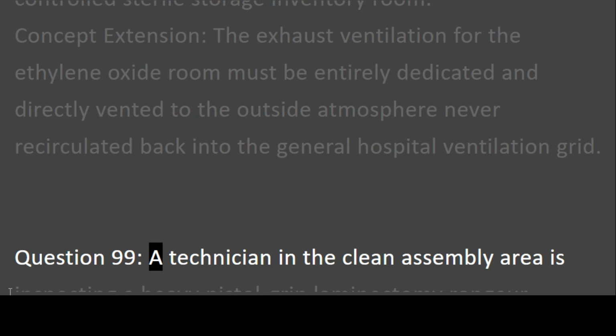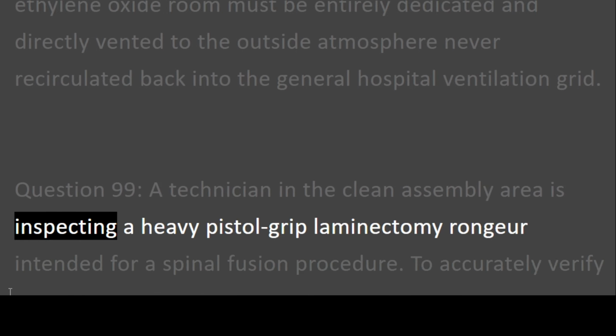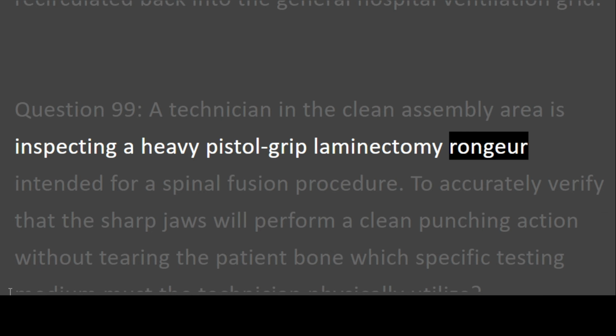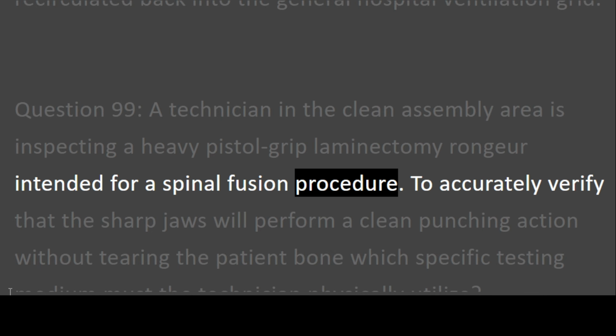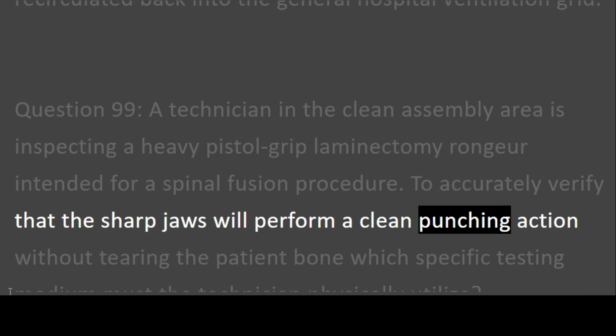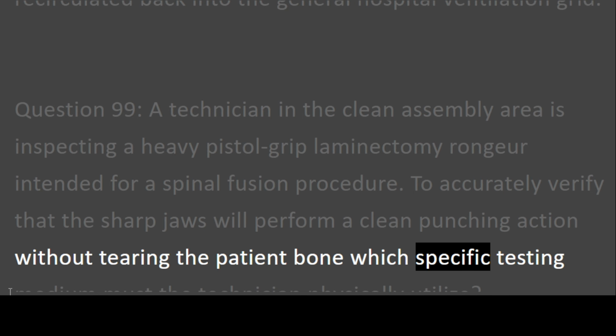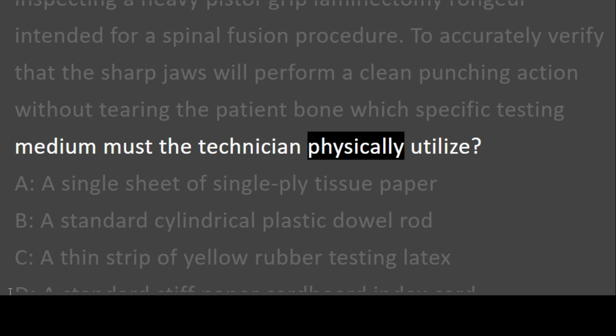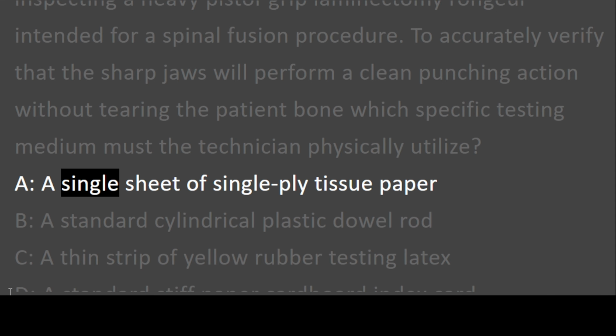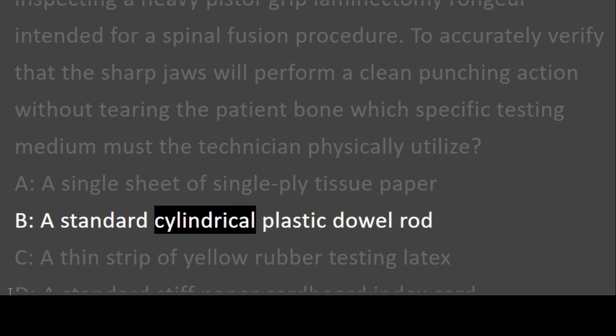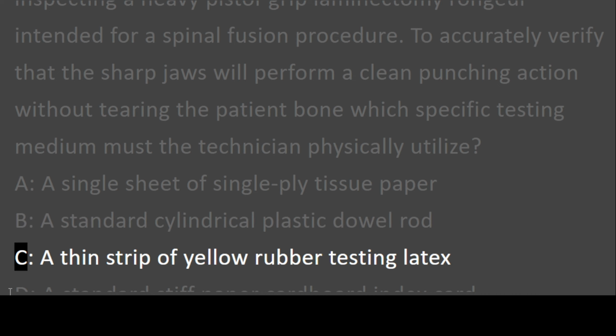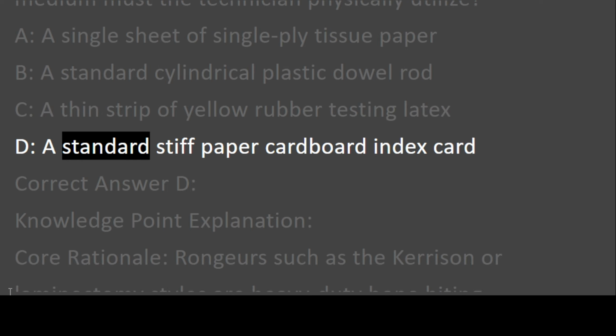Question 99. A technician in the clean assembly area is inspecting a heavy pistol grip laminectomy rongeur intended for a spinal fusion procedure. To accurately verify that the sharp jaws will perform a clean punching action without tearing the patient bone, which specific testing medium must the technician physically utilize? A. A single sheet of single-ply tissue paper. B. A standard cylindrical plastic dowel rod. C. A thin strip of yellow rubber testing latex. D. A standard stiff paper cardboard index card.